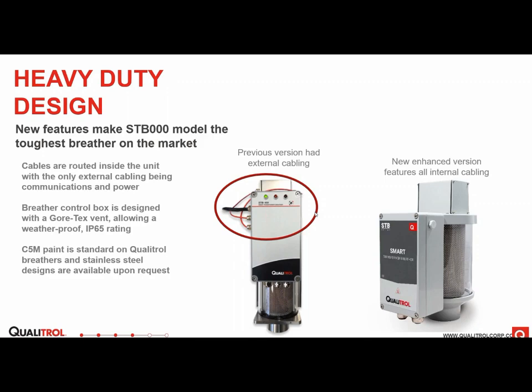No animals can have any impact on it. Fewer points of moisture ingress, so all of these connection points are potential leak paths. So it's an overall more robust design. In addition to that, we also made this control enclosure IP65 as a standard, and the entire breather is also C5M coated. C5M is kind of a standard for high durability corrosion protection.